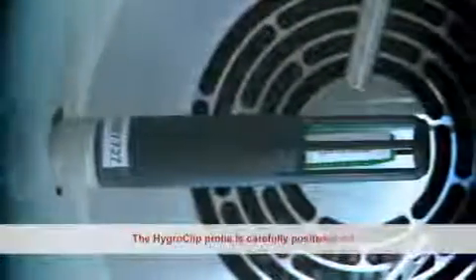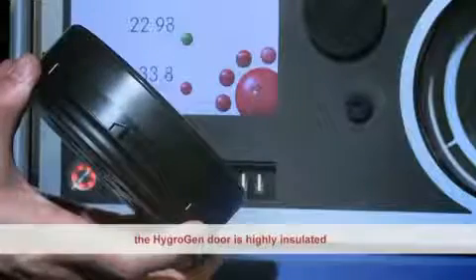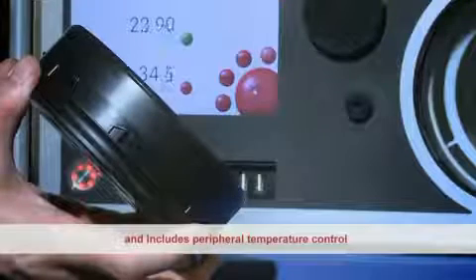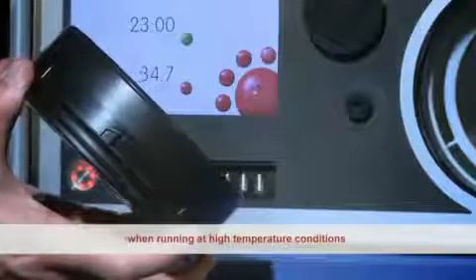The HygroClip probe is carefully positioned to provide the best possible chamber control. To achieve temperature stability and gradient specifications, the HygroGen door is highly insulated and includes peripheral temperature control to reduce temperature gradients and condensation when running at high temperature conditions.